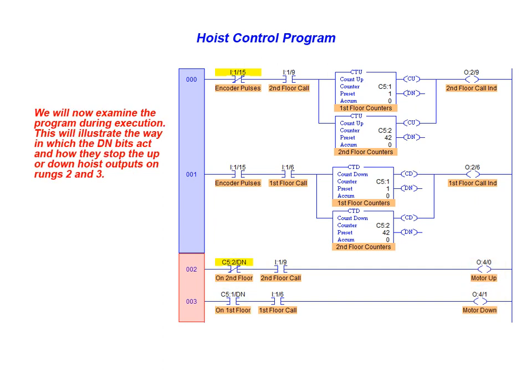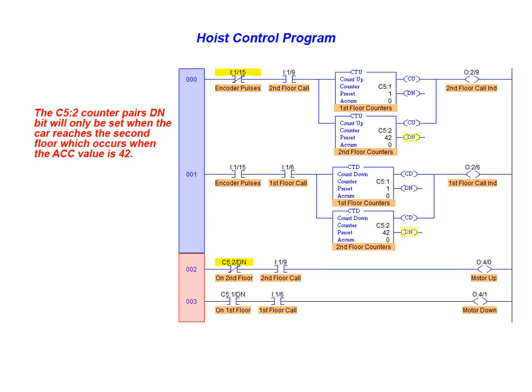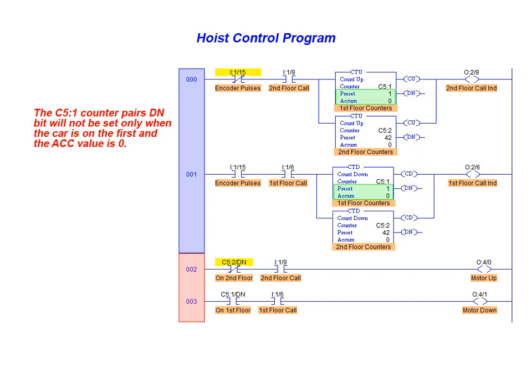We will now examine the program during execution. This will illustrate how the done bits act and how they stop the up or down hoist outputs on rungs 2 and 3. The C5-2 counter pair's done bit will only be set when the car reaches the second floor, which occurs when the accumulated value is equal to 42. The setting of the done bit breaks continuity on rung 2 and the motor hoist up action will be stopped. The only time that the C5-1 counter pair's done bit is unset is when the car is actually on the first floor and the accumulated value is zero. This means that an ongoing hoist down action will be stopped by the continuity being interrupted when the bit is unset on rung 3.